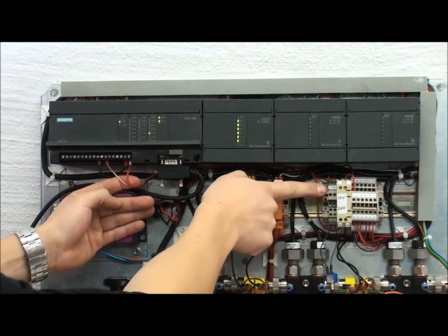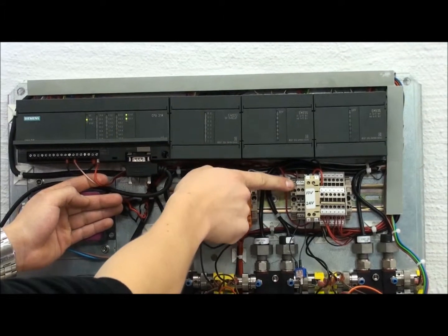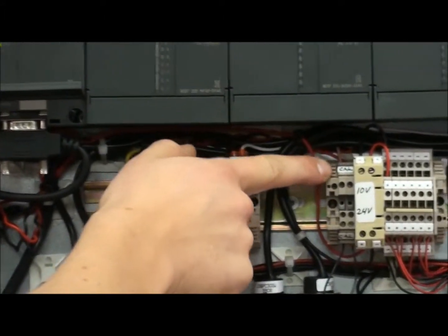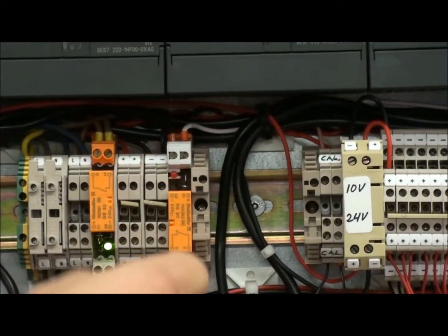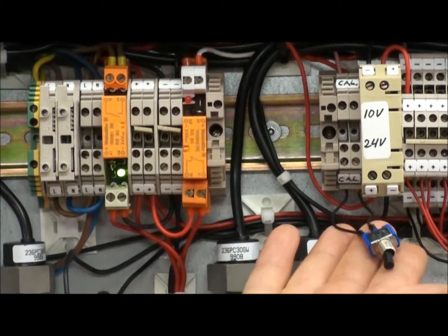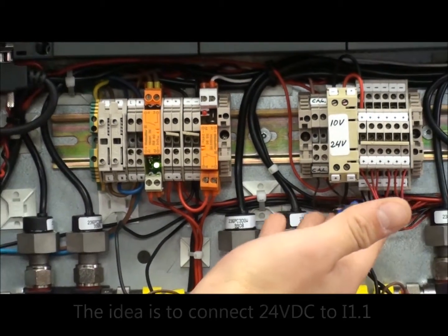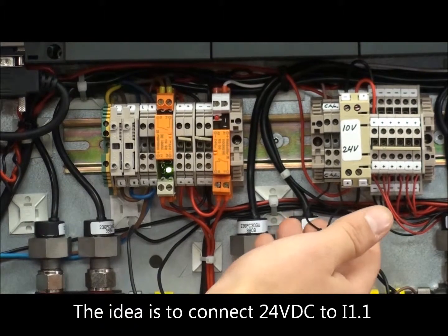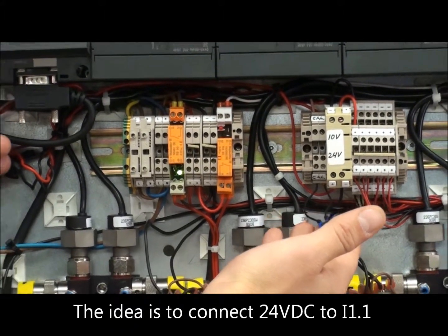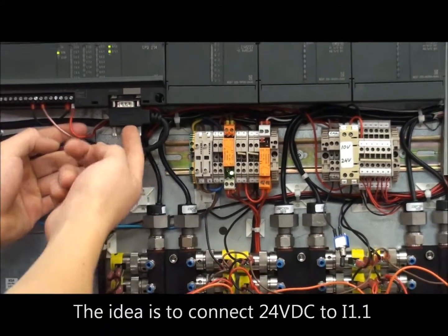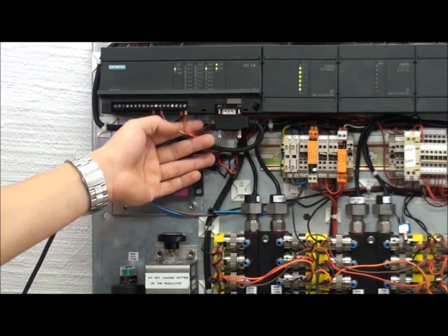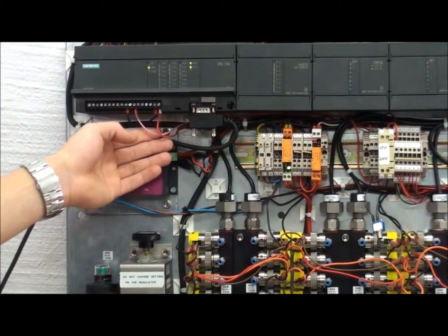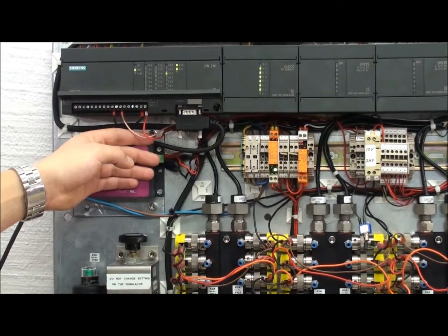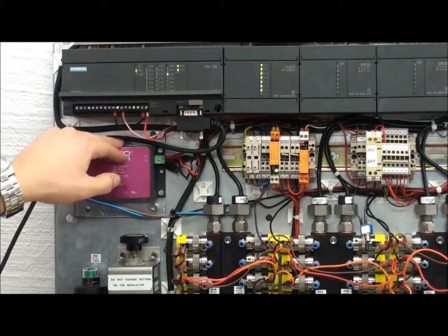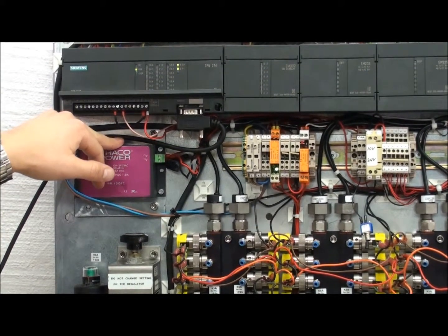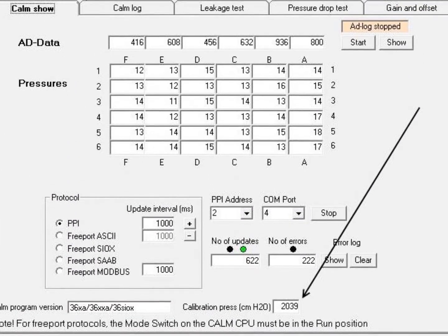And there is a terminal here which is called calibration. It's CAL for calibration. And then you put your switch here, just connect it there, because you're meant to do a jumper here. The next step is to check with CALM which is the calibration pressure. In this specific case, the calibration pressure is 2039 cm H2O.